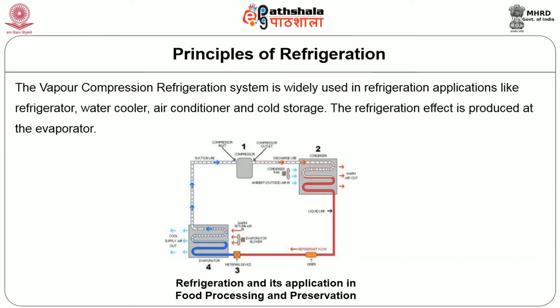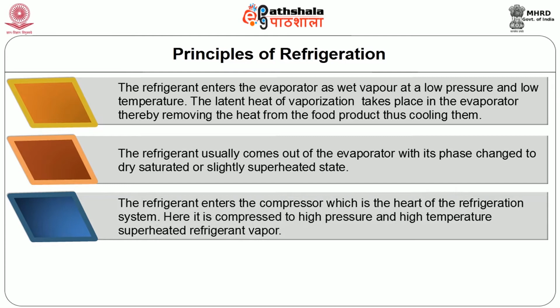The refrigerant enters the evaporator as a wet vapor at low pressure and low temperature. The latent heat of vaporization is absorbed in the evaporator, thereby removing heat from the food product and thus cooling it. The refrigerant usually comes out of the evaporator with its phase changed to a dry saturated or dry superheated state. The refrigerant enters the compressor, which is the heart of the refrigeration system. Here, it is compressed to a high pressure and high temperature superheated refrigerant vapor.